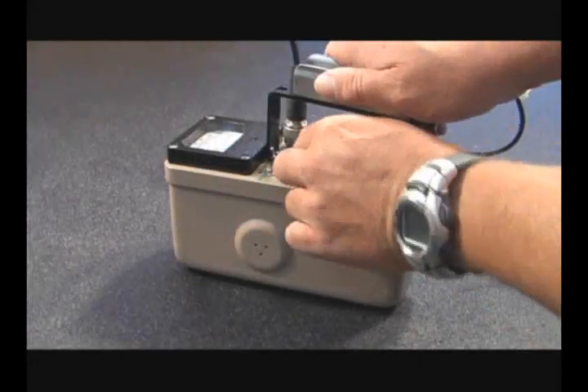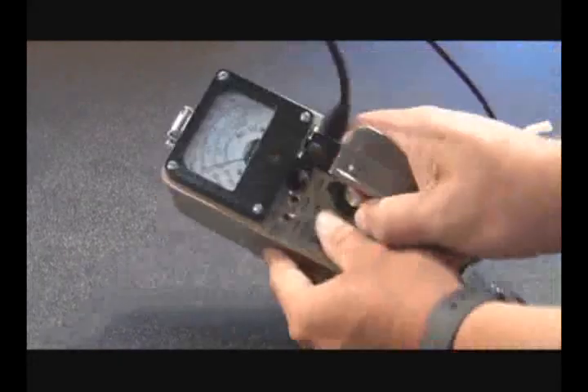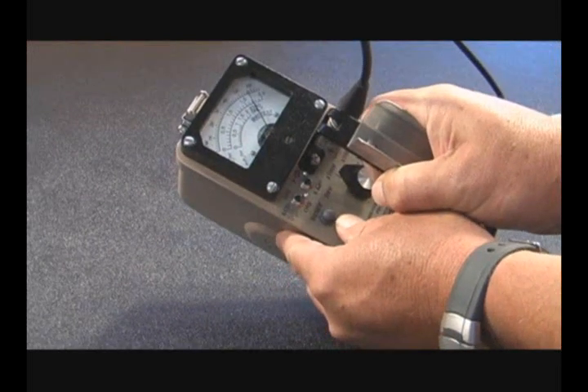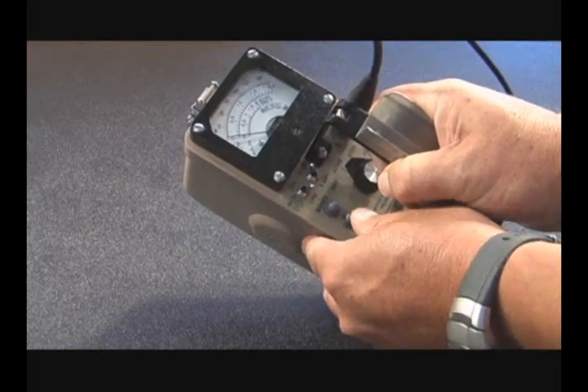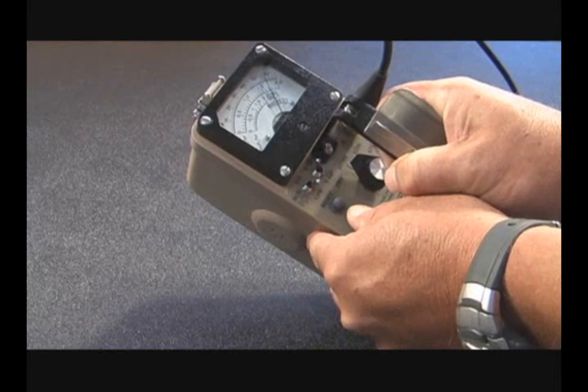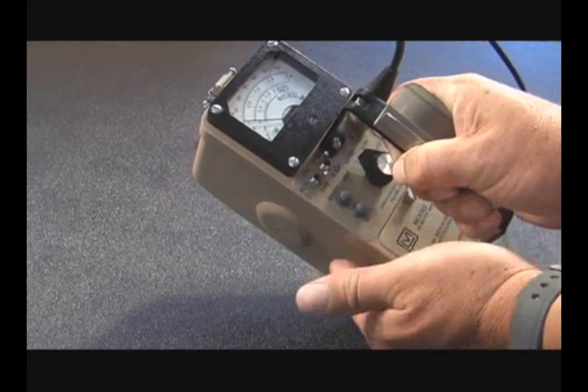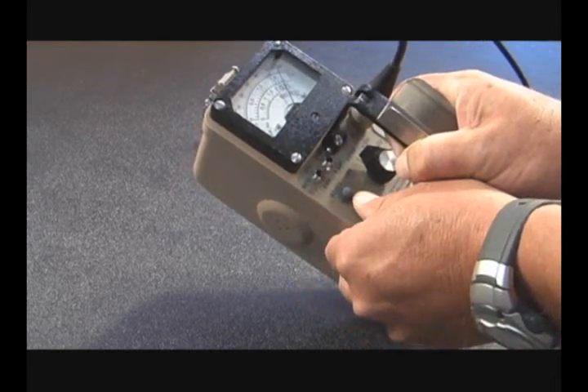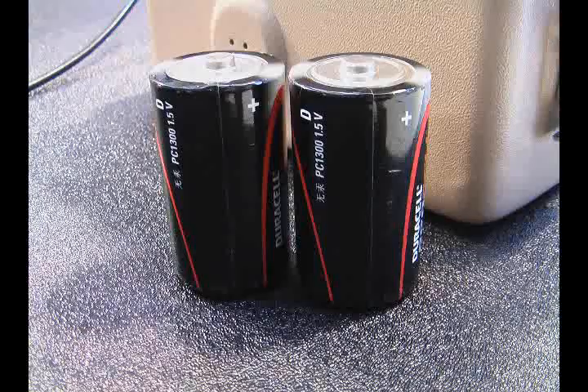The batteries should be checked each time the instrument is turned on. Move the range select to the times 1000 position and press the battery button. Ensure that the meter needle deflects to the battery check portion on the meter scale. If the meter does not respond, check to see if the batteries have been correctly installed. Replace the batteries if necessary.